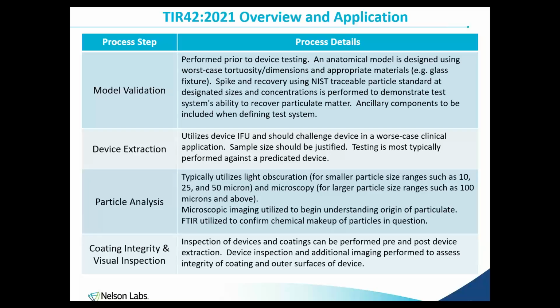And then another pretty big consideration in TIR42 is just overall device performance as it relates to something like coating integrity and just overall degradation of a device through use. So, you know, you could learn that running through your IFU is actually not working well with something like a new coating manufacturer change. So what we can do is we can run through a simulated use after we have initially dyed the coating using a stain.